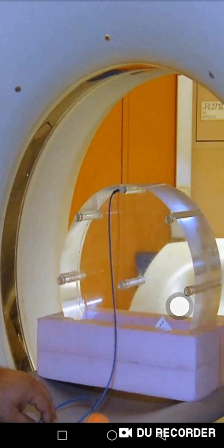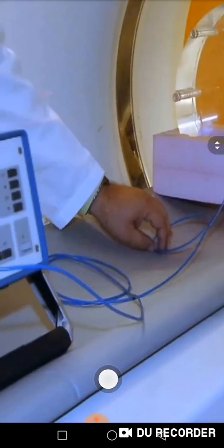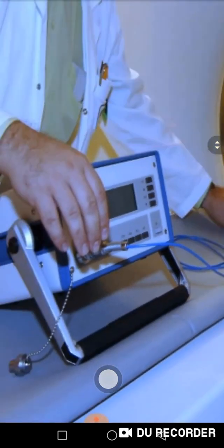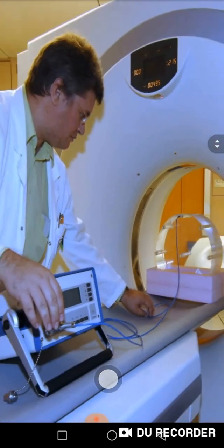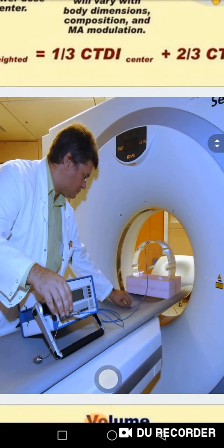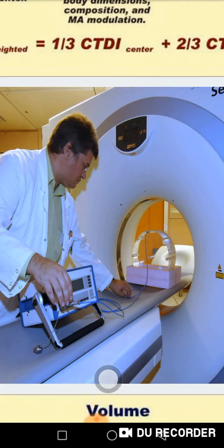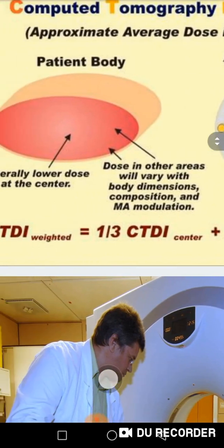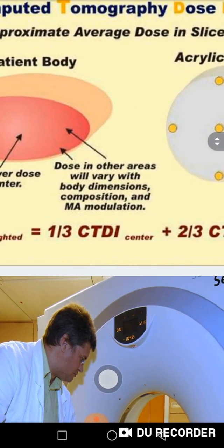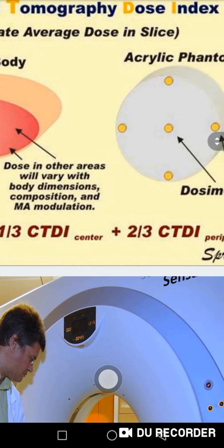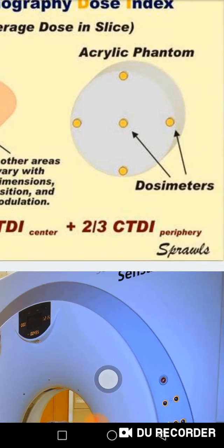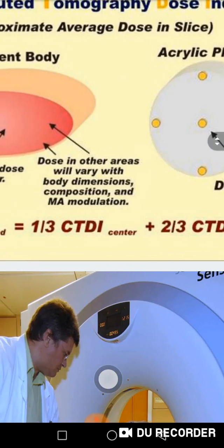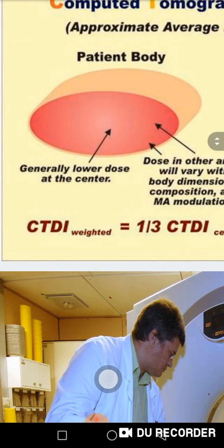I connect the ionization chambers to the monitor to measure the dose that will come to these parts. I adjust my machine to a specific milliampere and certain parameters to see how much dose reaches this phantom, which represents the patient. Through this equation, the weighted CTDI index is one-third of the central dose plus two-thirds of the peripheral dose — giving you the weighted CTDI index.